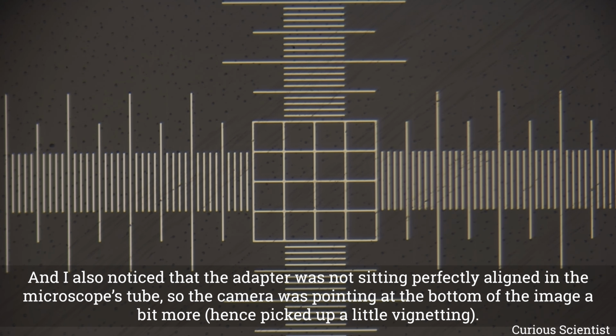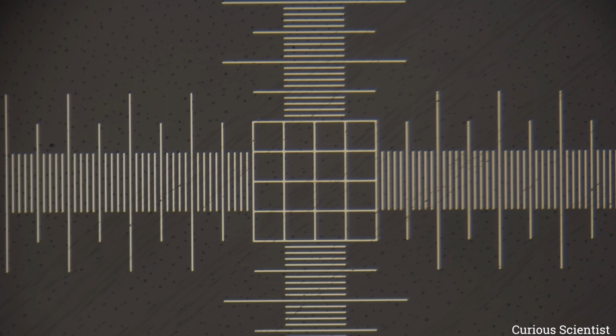So the lines are really nice and straight and parallel as they should be. And we are still looking at the same calibration slide. Nothing changed. I even used some blue tack to hold down the slide so it's not moving anywhere. I did not move the stage. So this is what we see. You can see that the field of view is reduced because we magnified the image a bit. We can think about this as cropping some percentage of the image out. Like when you put a full frame lens on an APS-C camera, you also experience a cropping factor, typically around 1.4 to 1.6, because of how these lenses project the image. And kind of the same happens in this scenario. Maybe it's not exactly the same, but kind of the same. So this is what we can see here.